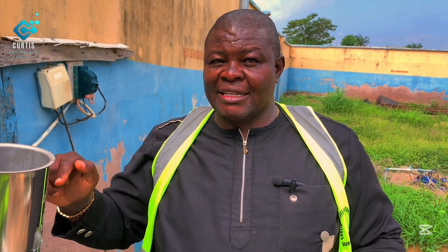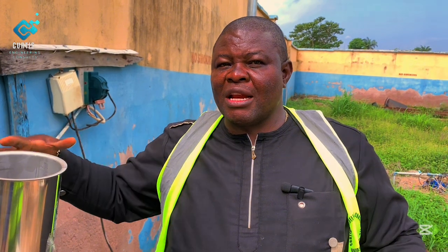So it is the membrane that does the work, and the membrane is permeable. What's called permeability is that it's not a fluid system; it permeates. So the water that will now get into the system must be the one that is already pure and clean. Then it will be transmitted from the center of this point. So every other deposit will be hanging at the membrane. And after a while, 6 months, 1 year, 2 years, the membrane will be removed and cleaned.